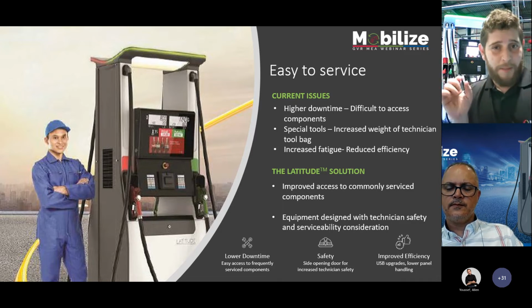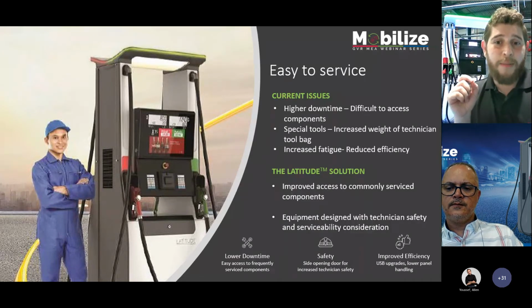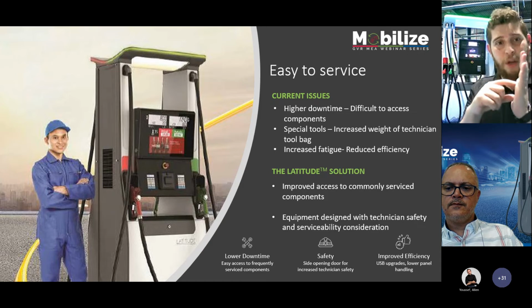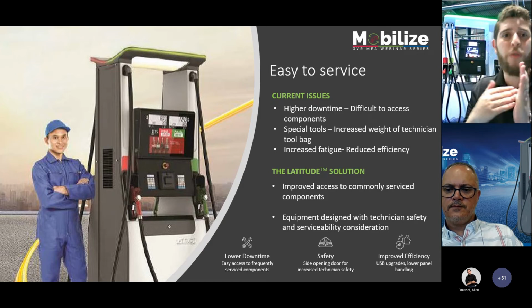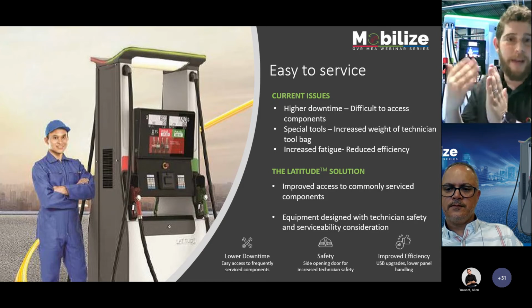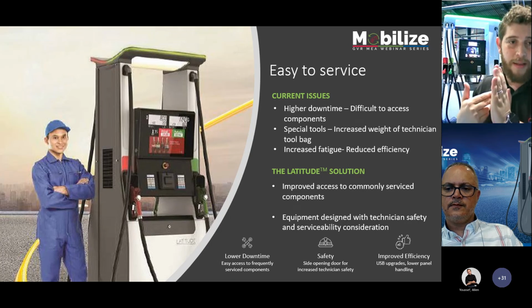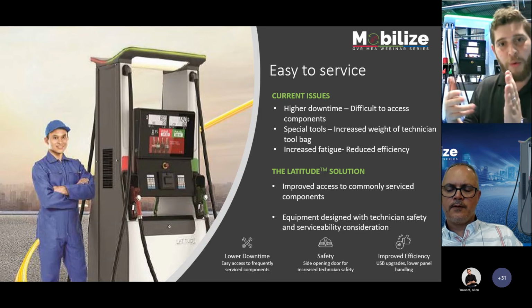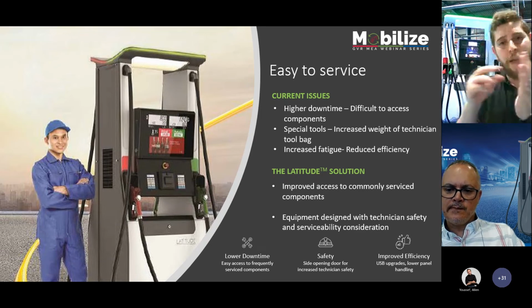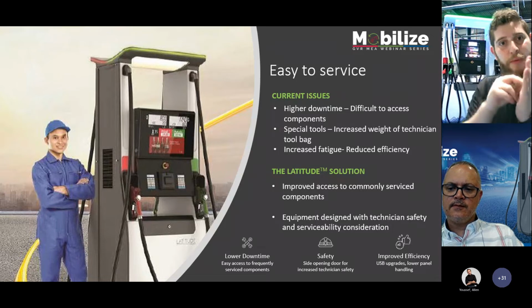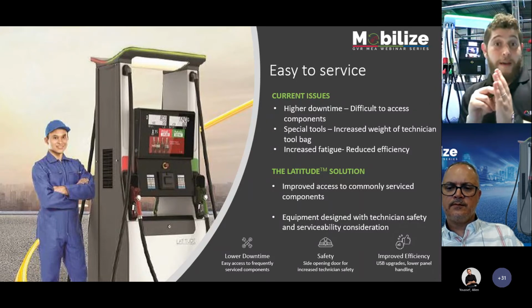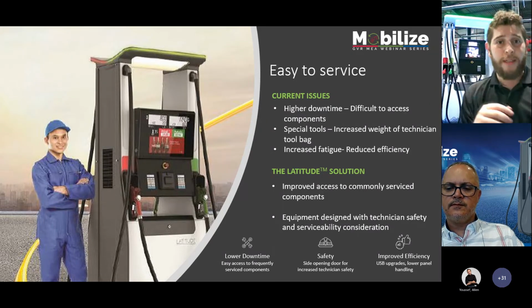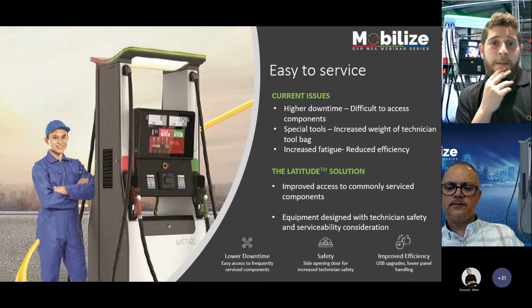Another point, which is small but makes a big difference, is cable management inside the pumps. It's done very nicely, and the clamps that fix the cables inside the pump are reusable. So once the pump is in service and somebody has to change a cable and cuts the clamp, it normally becomes a mess and gets messier with every intervention. But with reusable clamps, when you change a cable, you simply remove the clamp, change the cable, and put the clamp back on.